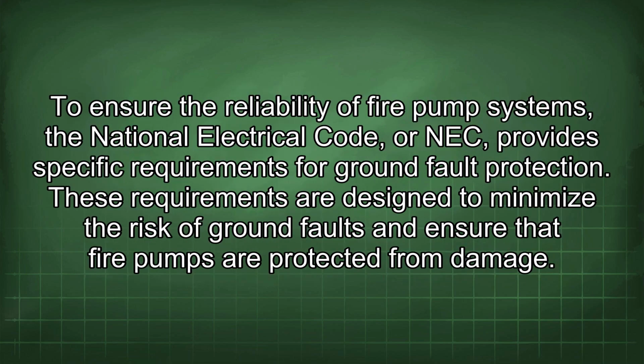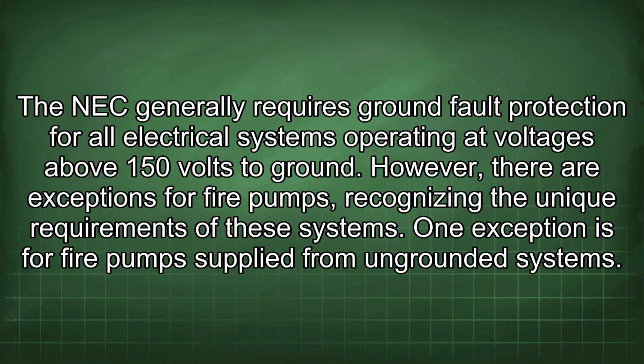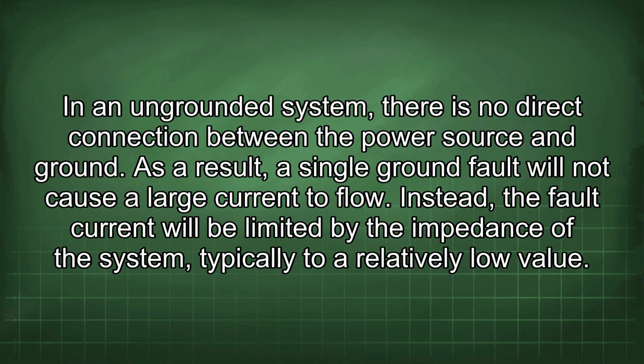To ensure the reliability of fire pump systems, the National Electrical Code, or NEC, provides specific requirements for ground fault protection. These requirements are designed to minimize the risk of ground faults and ensure that fire pumps are protected from damage. The NEC generally requires ground fault protection for all electrical systems operating at voltages above 150 volts to ground. However, there are exceptions for fire pumps, recognizing the unique requirements of these systems. One exception is for fire pumps supplied from ungrounded systems. In an ungrounded system, there's no direct connection between the power source and ground.